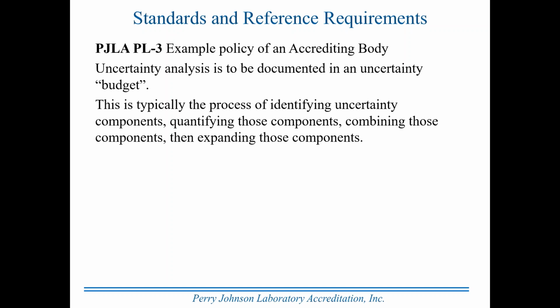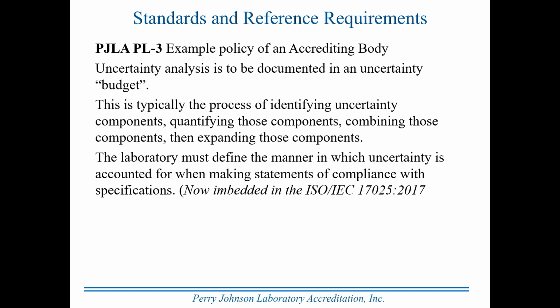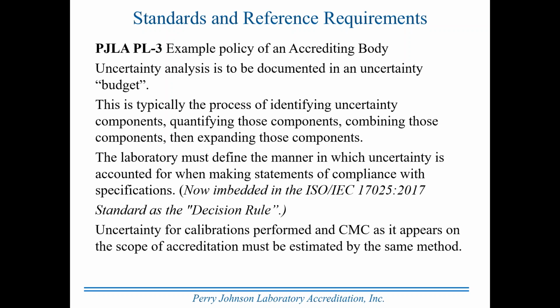The budget is typically the process of identifying uncertainty components or contributors, quantifying those components, in other words, putting numbers to how much they contribute, combining those components, then expanding those components and getting ultimately an expanded measurement uncertainty. The laboratory must define the manner in which uncertainty is accounted for when making statements of compliance with specifications. This was a requirement in the previous version. It is now embedded in what's called a decision rule in the new standard.